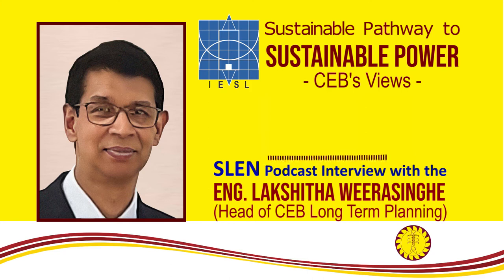Actually, system operators do not intervene to maintain this balance at the seconds to millisecond scale. It is taken care of by the stored kinetic energy in the generators, mainly. So when customers suddenly ask for more electrical power in the next second, or start using less power than in the last second, it is the stored kinetic energy that gets converted to electrical power in the generators before the prime movers that are coupled to the generators.